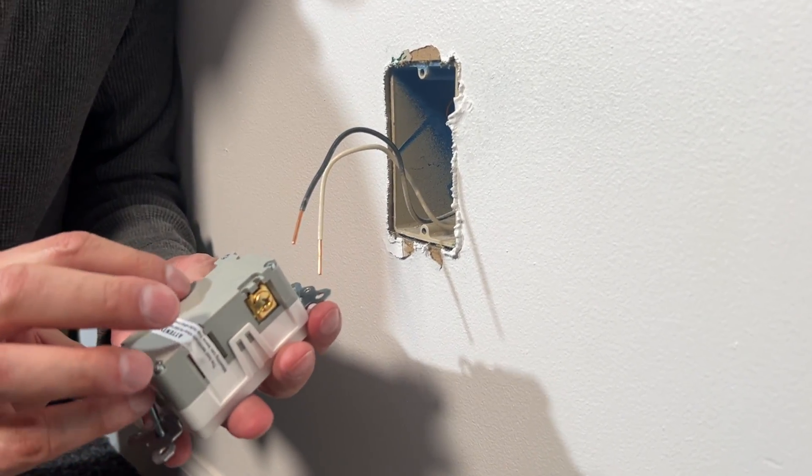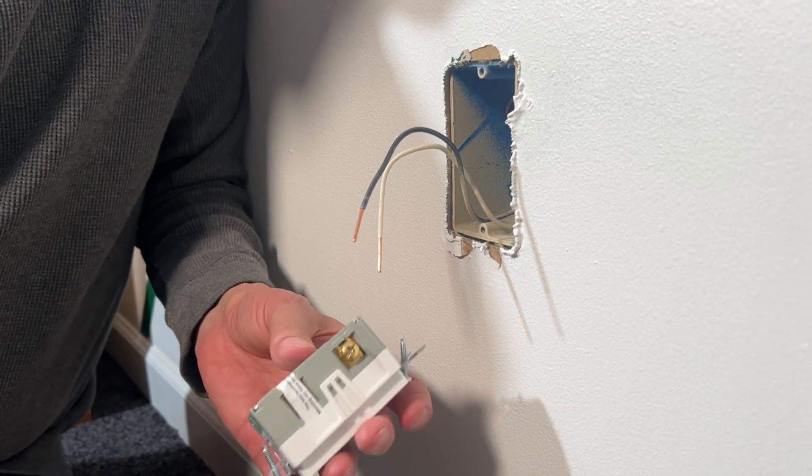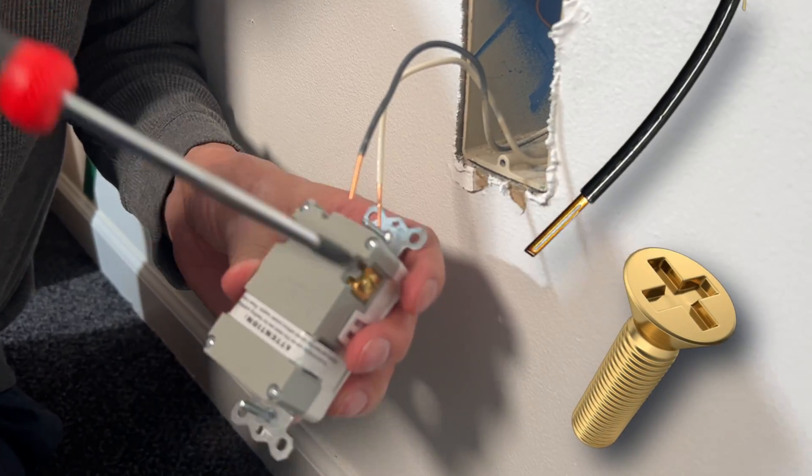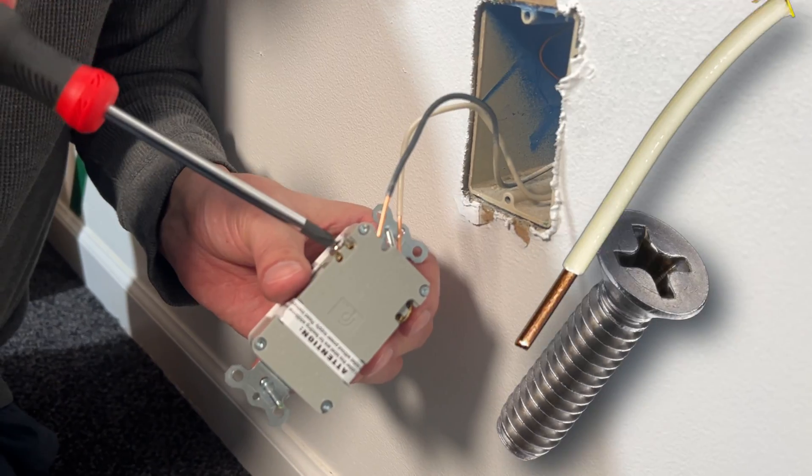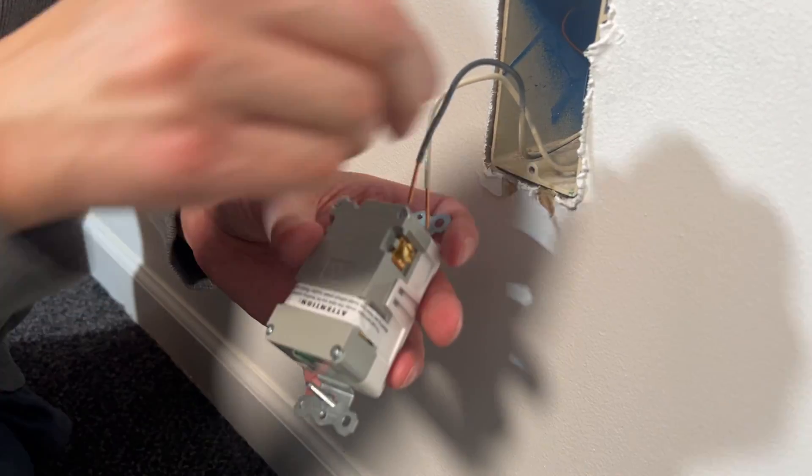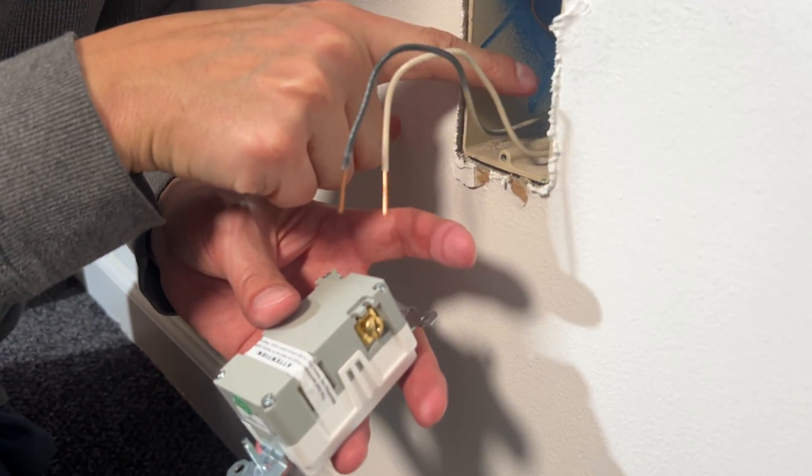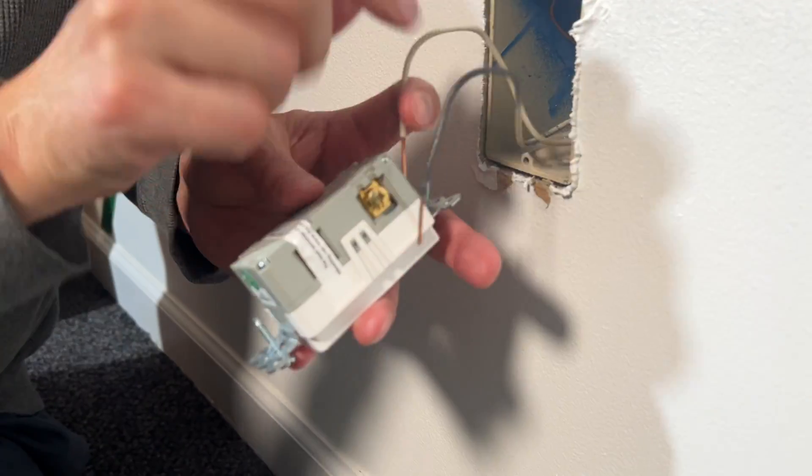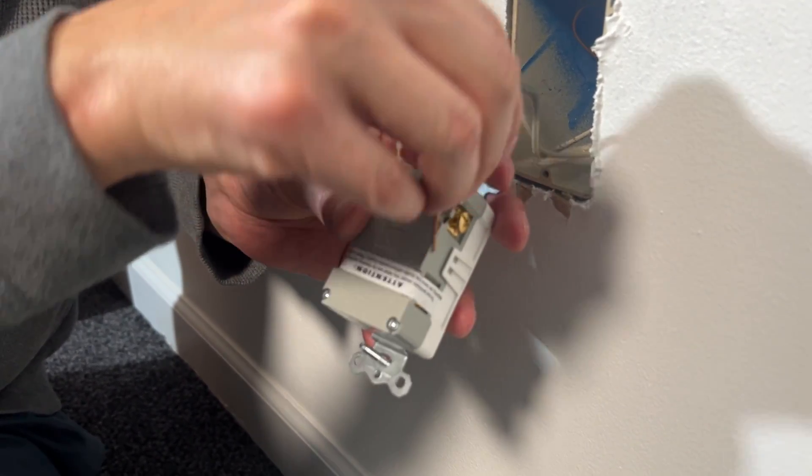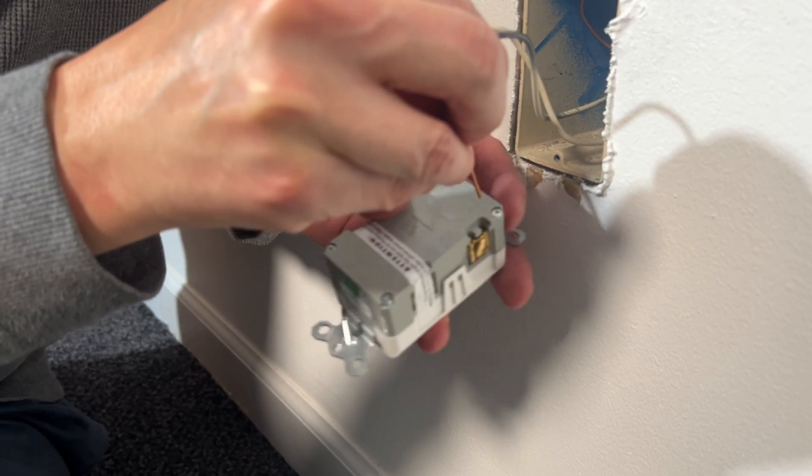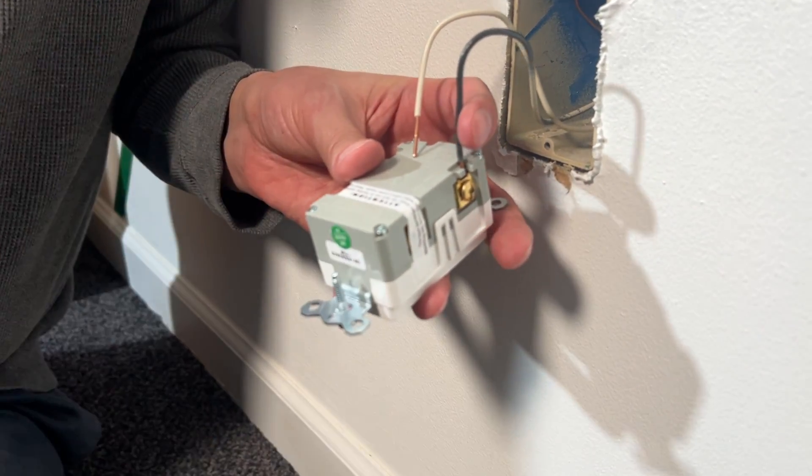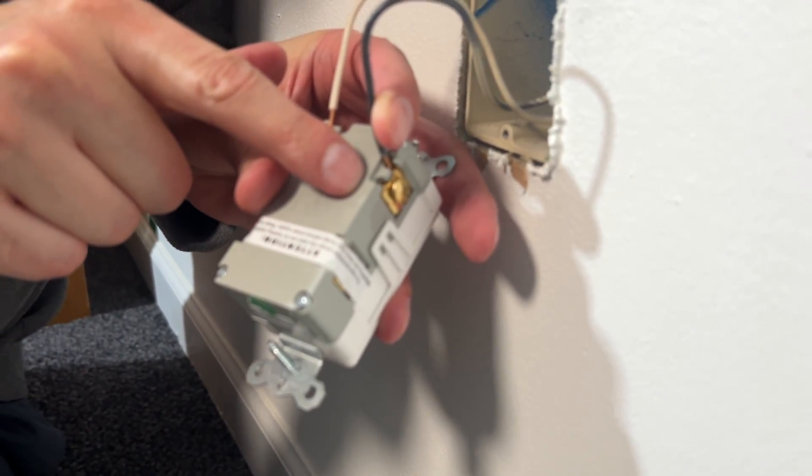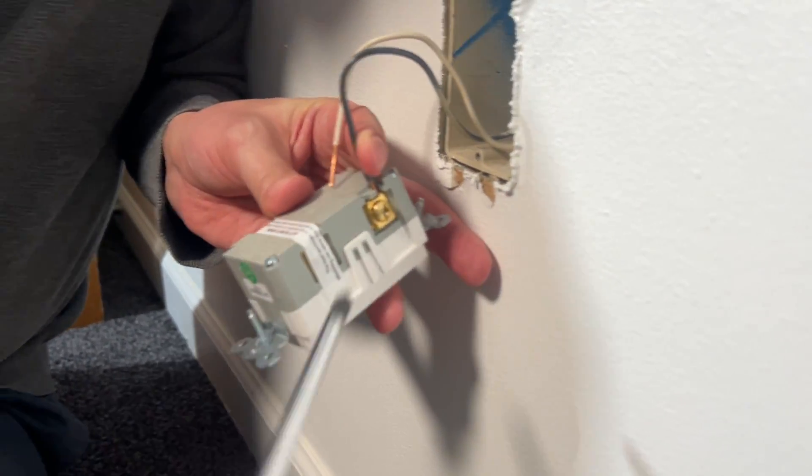Okay, now in the back of your GFCI outlet, they're really well designed. You simply loosen up the screws. The gold screw will be the black wire. The silver screw will be the white wire. So it's color coded. Now, you may have extra wires in the box going to other outlets. You are going to want to include and attach that here. Otherwise, your other outlets in the same room may not have power. So this is where you will put the other wires if you have additional wires to other outlets.